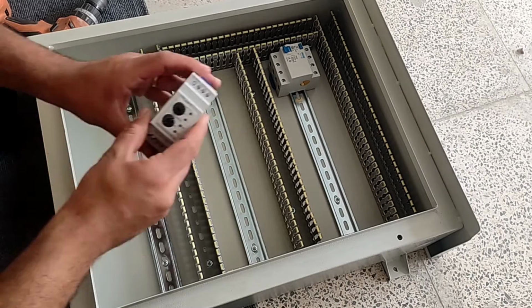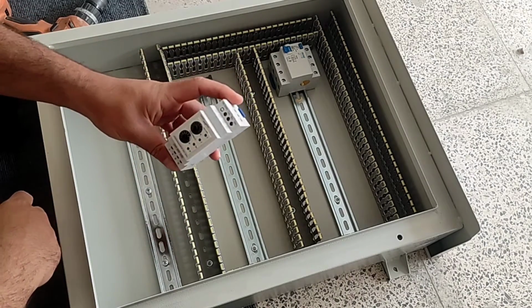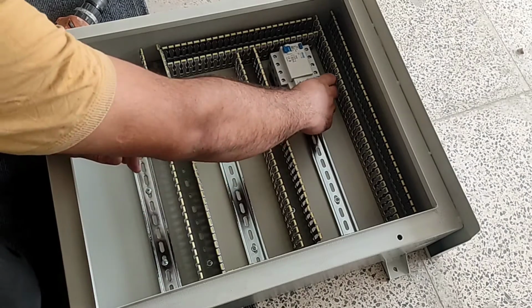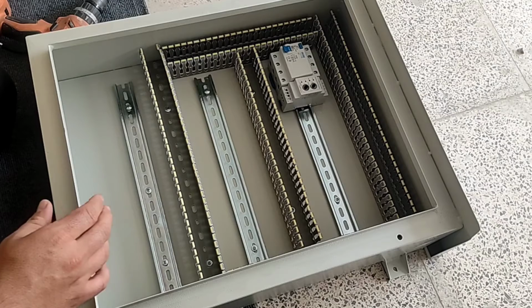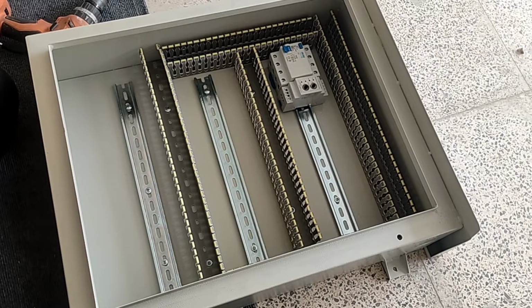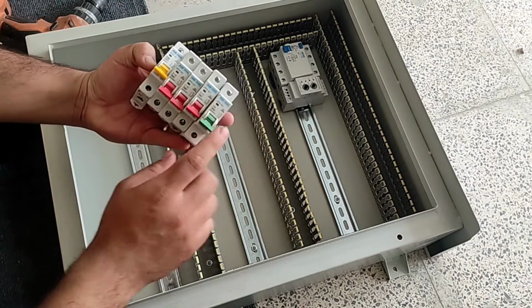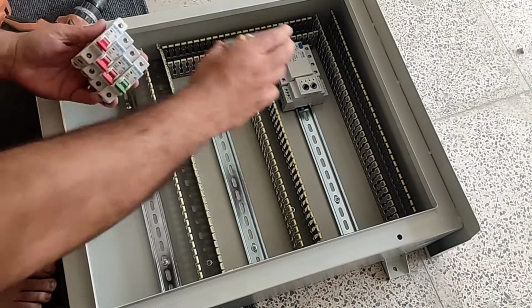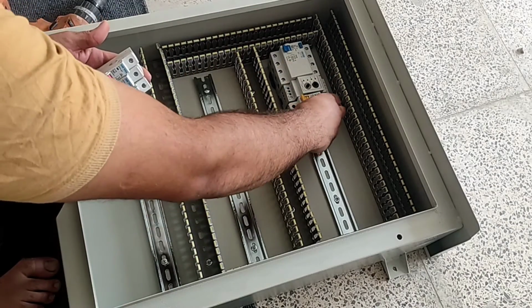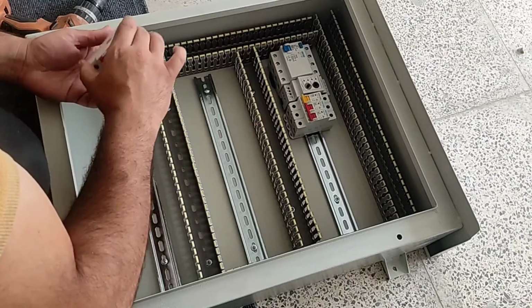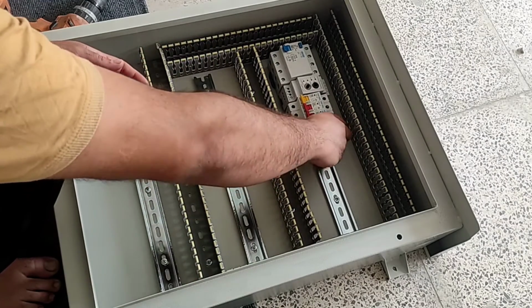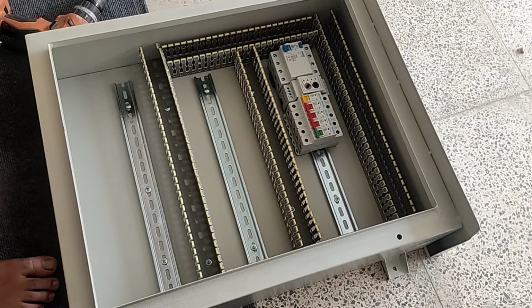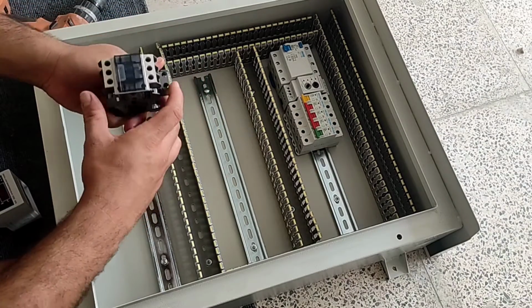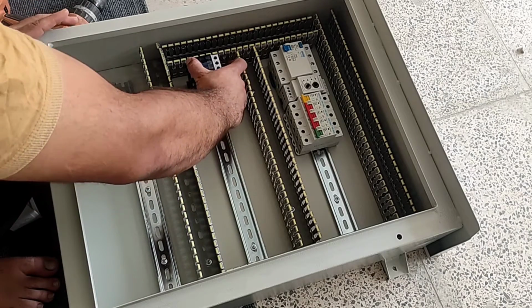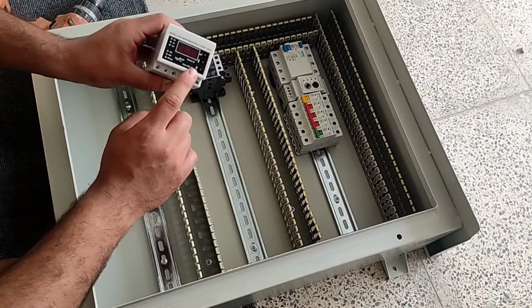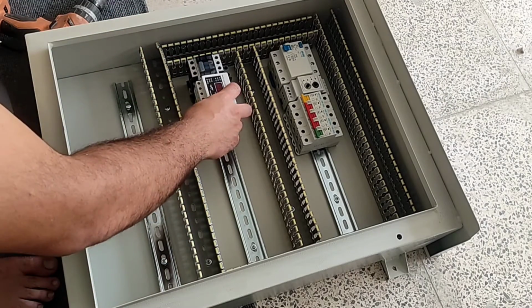In addition, we install a 3-phase monitoring relay that protects the 3-phase consumer against 2-phase or voltage decrease and increase. For single-phase outputs, we use several single-phase miniature switches. These switches protect the circuit from short circuit. We also use a contactor for 3-phase output. In order to determine the current of the 3-phase consumer, we use a current controller relay that protects the consumer from excess current.